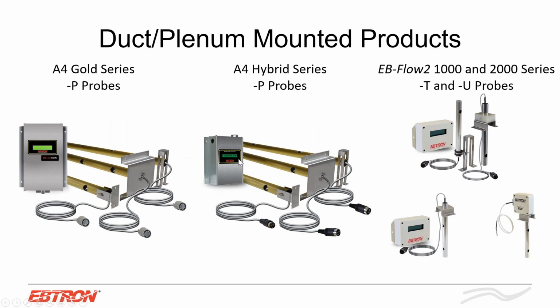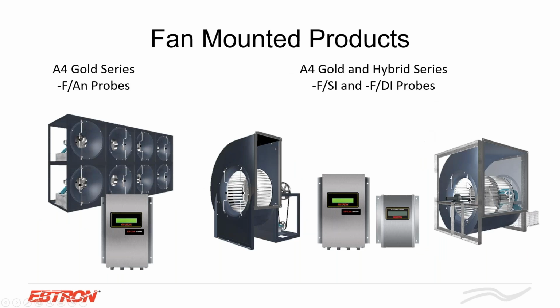And we also have duct mounted products, and this is kind of the EBTRON bread and butter. I talked about the Gold series with the humidity. That's going to give you the most accurate device because we have up to 16 sensor nodes, so we can read an accuracy of plus or minus 3% for ducted applications up to 120 inches by 120 inches. Have the Hybrid series. This I see is more for monitoring. If you're trying to achieve a LEED point and you're not controlling, this is a little bit more cost effective than this. And again, this is our more application specific products.